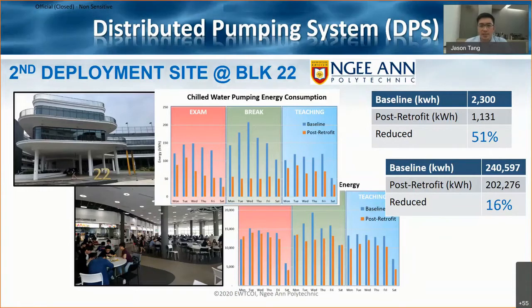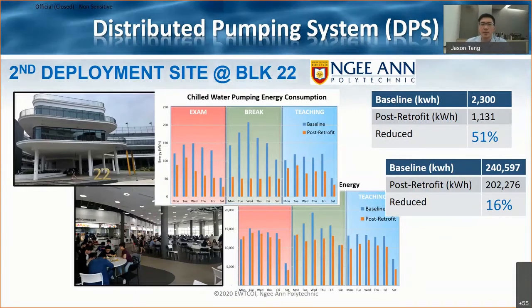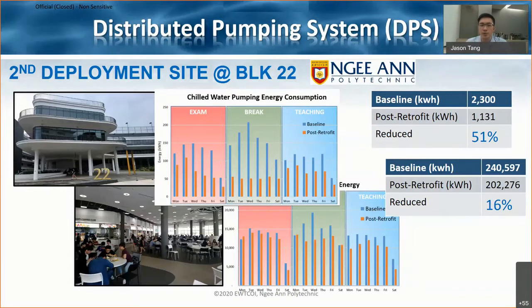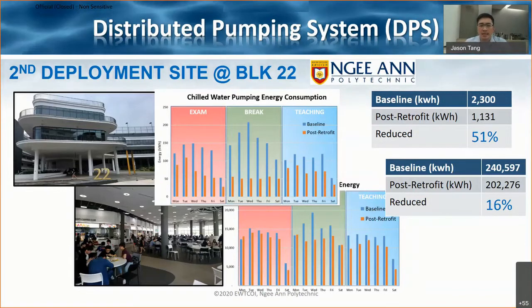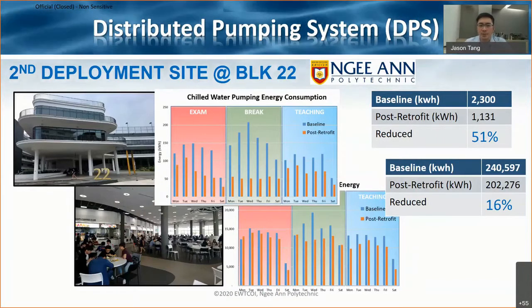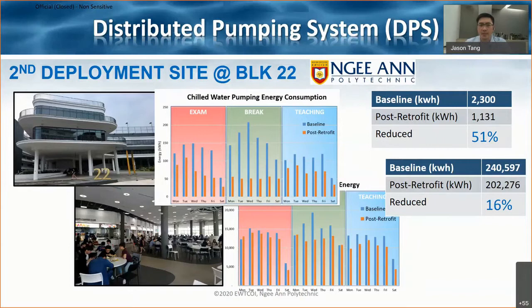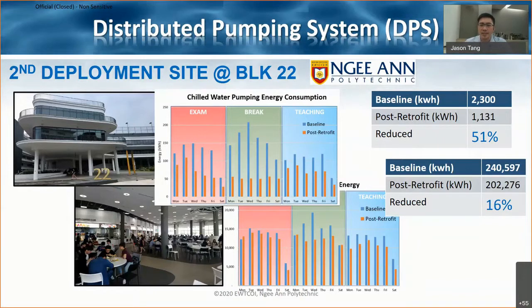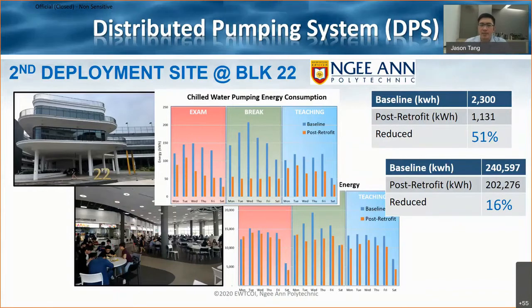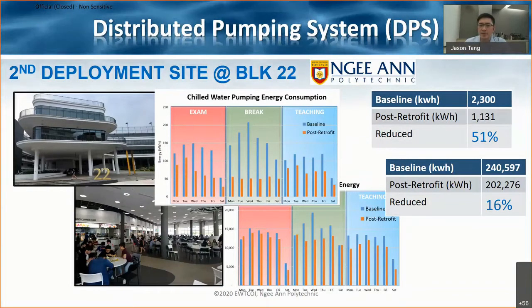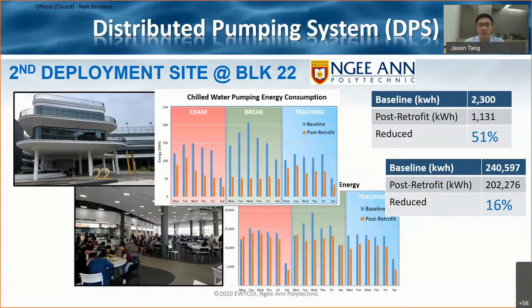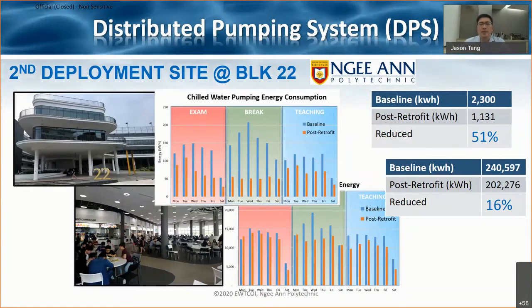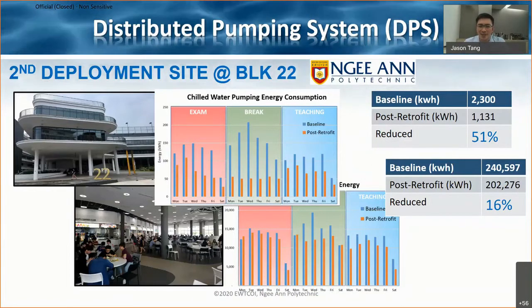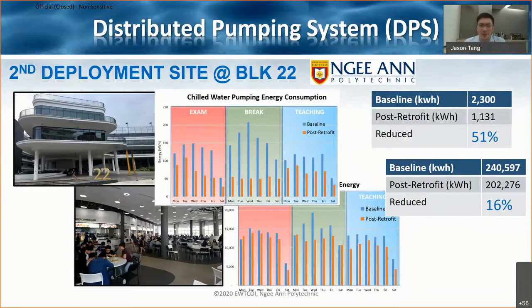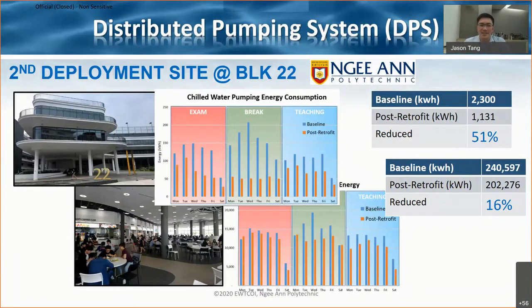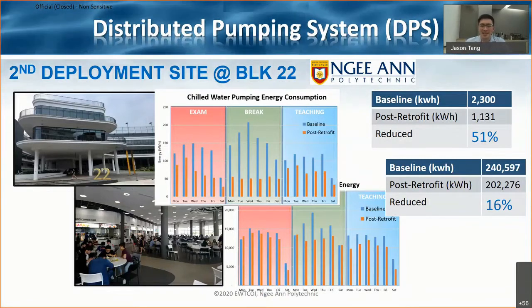This is really just pushing water through the whole system, because you're looking at centrally cooled systems using chilled water to cool the building. In our second deployment site - the first was in Grundfos's own building, a low-story office and factory setup, only 2 stories - the effect isn't really seen, because pumping needs in buildings relate to the height of the building. With only 2 stories, there isn't much head to pump up. An 8-story building isn't ideal either - they were hoping for a 30 or 40-story building.